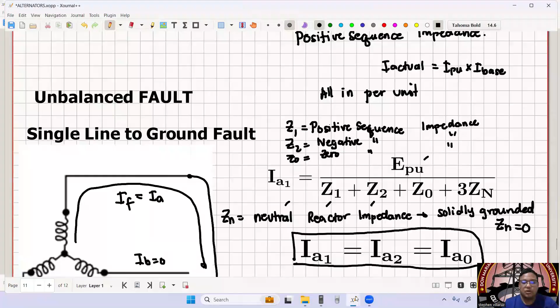Let's solve number 34. Given: 600 kVA, so our S is 600 kVA, 2,400 volts line-to-line voltage. Three-phase alternator has a zero sequence reactance of 12%, meaning Z0 is 0.12 per unit. Positive and negative sequence reactances of 8%, so Z1 is 0.08 per unit and Z2 is 0.08 per unit. If the alternator resistance is negligible, RA is 0.